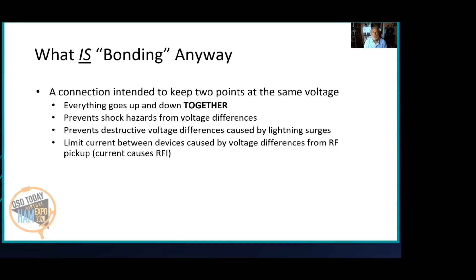So you want to minimize those by bonding stuff together so that everything goes up and down together. That's a recurrent theme of this talk. And by keeping the voltage differences between devices to an absolute minimum, what causes current flow? Voltage differences. So since RF pickup causes voltage and the current causes RFI, if I can minimize my voltage differences, I can also minimize the current and any problems it causes. Most RFI is caused by current, not voltage. So let's minimize the voltage differences by bonding, keeping everything together. We can also work in our favor for RF. It sounds hard and expensive, but it's really not. And the good news is that working on bonding works in your favor for AC safety, lightning protection, and RF management.